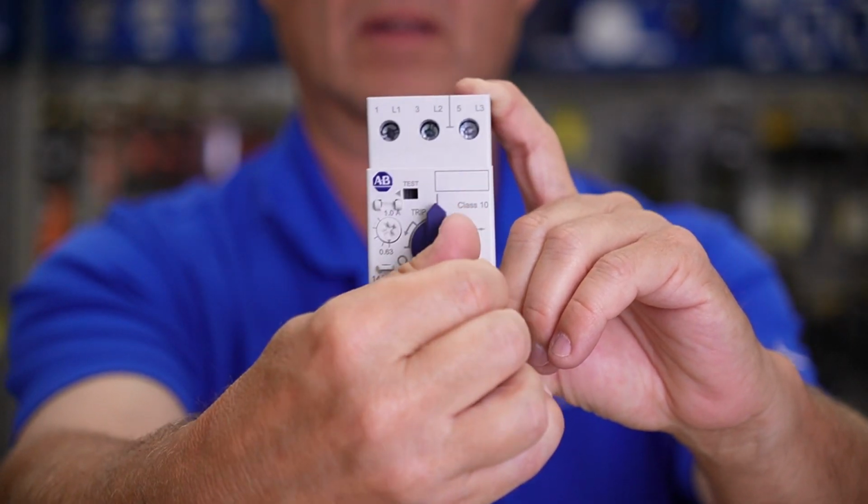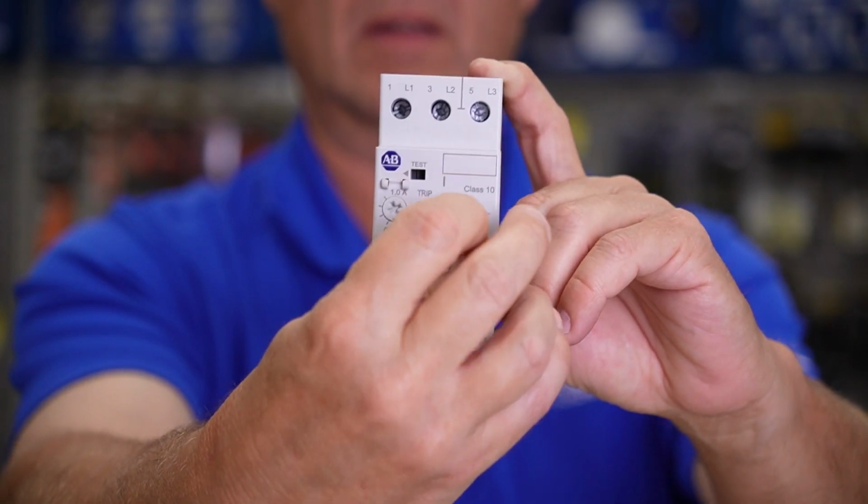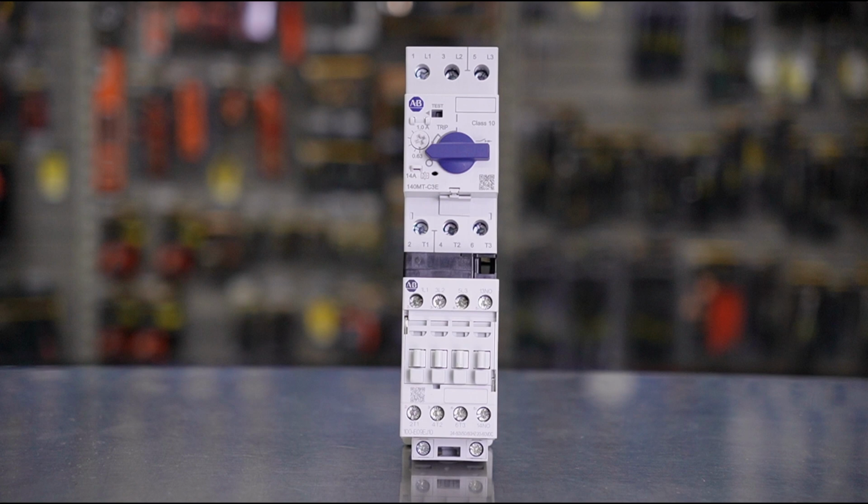This unique design gives you complete protection for your motors without the need for adding any additional circuit breaker or overload relay. In a nutshell, the MPCB is an all-in-one motor and branch circuit protective device that can be used as a standalone one-piece manual motor starter and disconnect, or in a two-piece motor starter that's combined with a contactor.